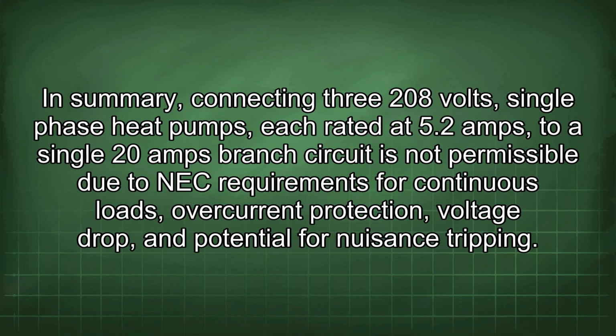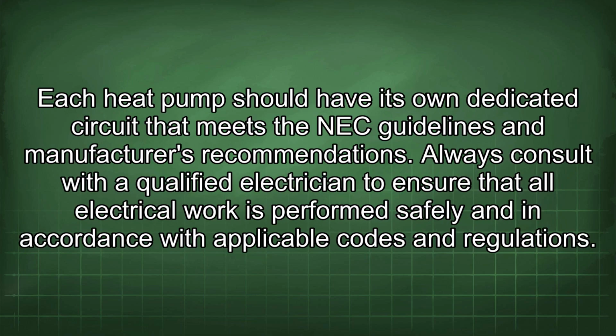In summary, connecting three 208 volt single-phase heat pumps, each rated at 5.2 amps, to a single 20 amp branch circuit is not permissible due to NEC requirements for continuous loads, overcurrent protection, voltage drop, and potential for nuisance tripping. Each heat pump should have its own dedicated circuit that meets the NEC guidelines and manufacturer's recommendations. Always consult with a qualified electrician to ensure that all electrical work is performed safely and in accordance with applicable codes and regulations.